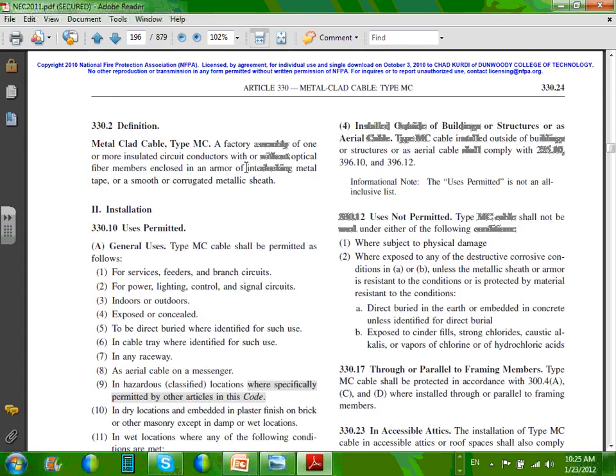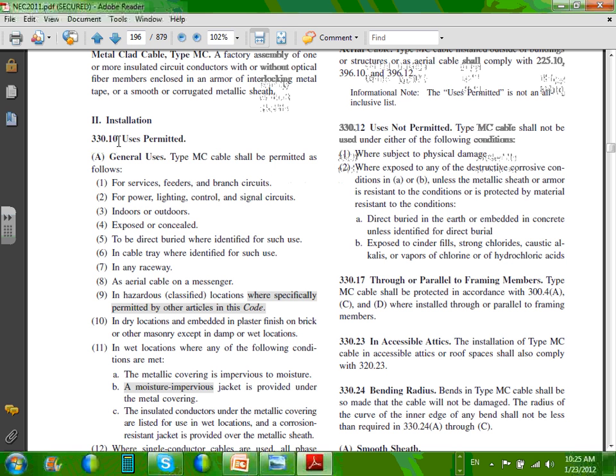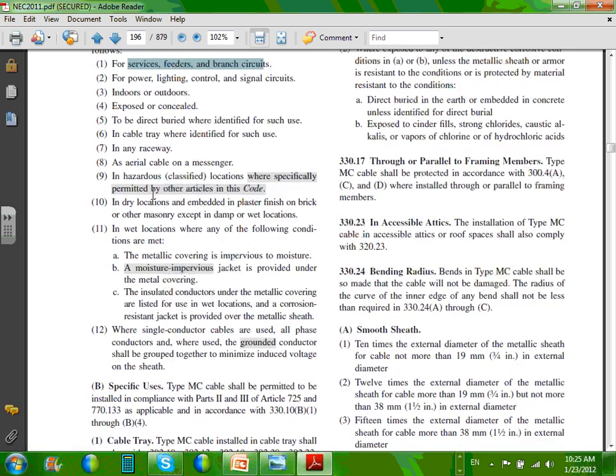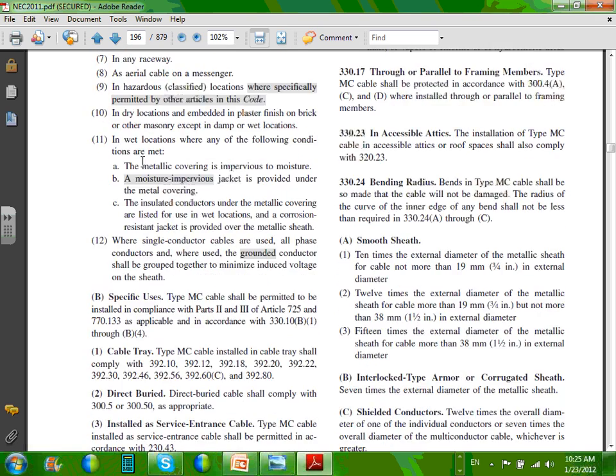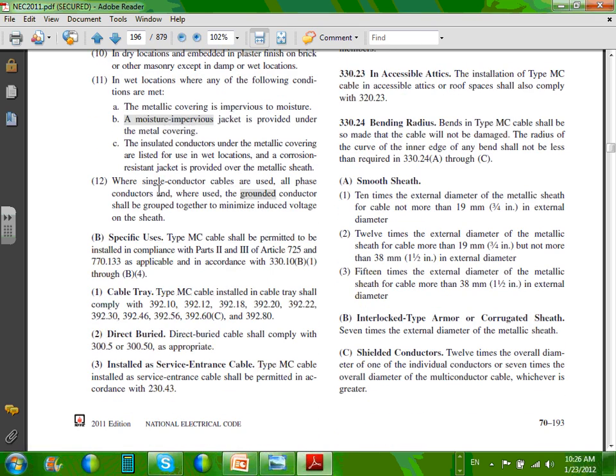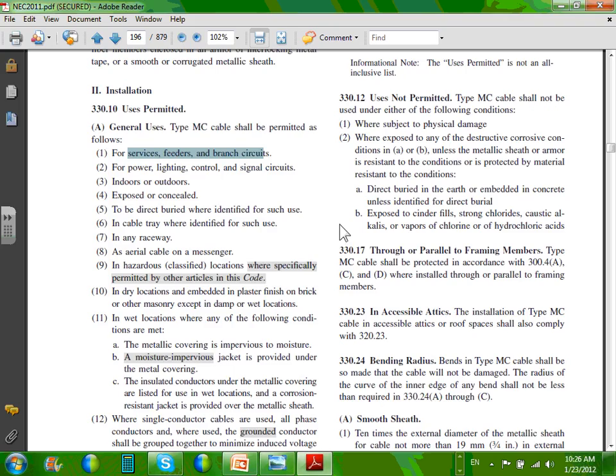MC cable. The first thing you're going to encounter, guys, when you use MC cable is, can you guys see that dot here? This article always ends up with dot 10. If it's dot 10, that will tell you where you can use this wiring method. Uses permitted. For service, look at this. Service, branch. This is one of the major ones that you can use. You can use it for service, feeders, and branch circuits, and it goes all the way. So whereas you can use it, direct buried, all the way.